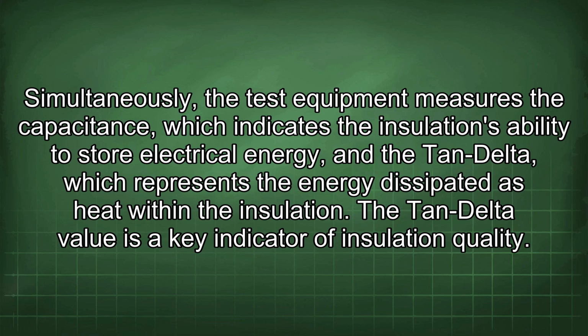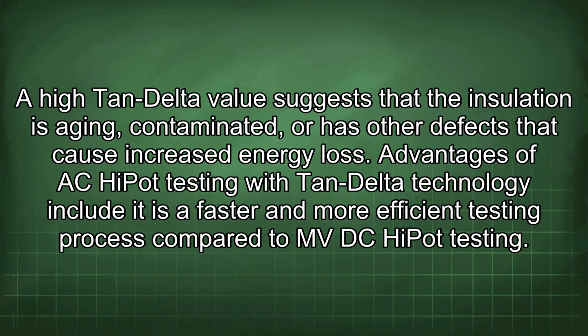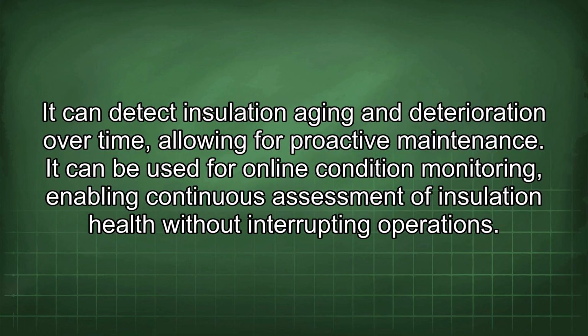The tan delta value is a key indicator of insulation quality. A high tan delta value suggests that the insulation is aging, contaminated, or has other defects that cause increased energy loss. Advantages of AC HiPot testing with tan delta technology include it is a faster and more efficient testing process compared to MVDC HiPot testing. It can detect insulation aging and deterioration over time, allowing for proactive maintenance. It can be used for online condition monitoring, enabling continuous assessment of insulation health without interrupting operations.